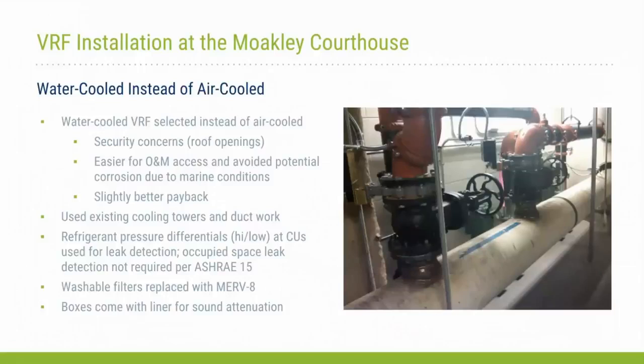It also allowed us to use a refrigerant pressure differential on the high-low at the cooling units for leak detection rather than the occupied space leak detection required by ASHRAE 15. A little bit on the maintenance side, because looking at operational excellence, we replaced some washable filters with MERV 8 filters, and our boxes there came with a liner for sound. Next slide, please.